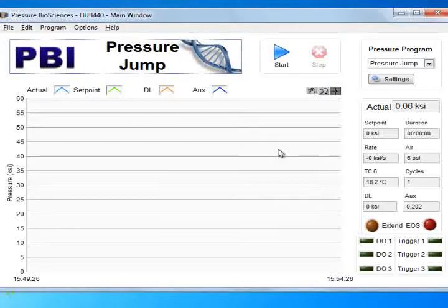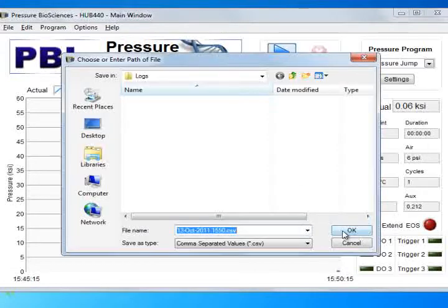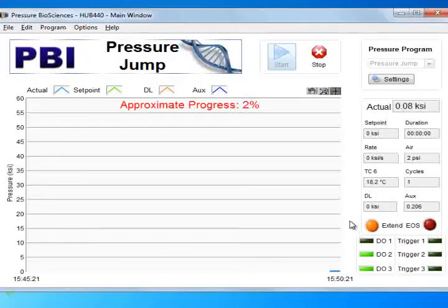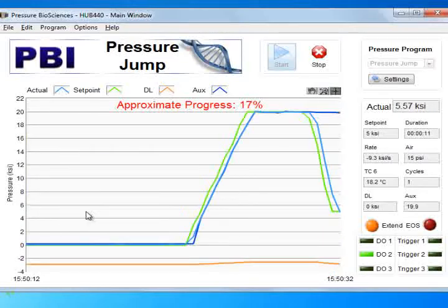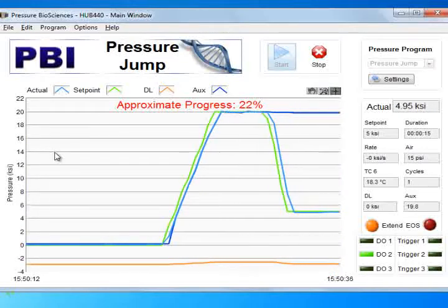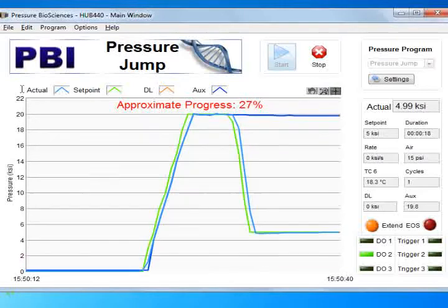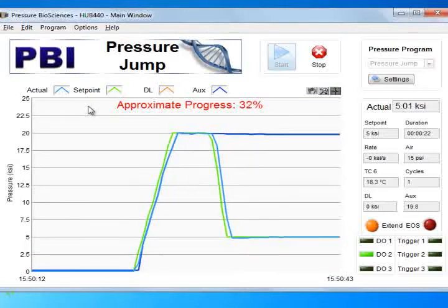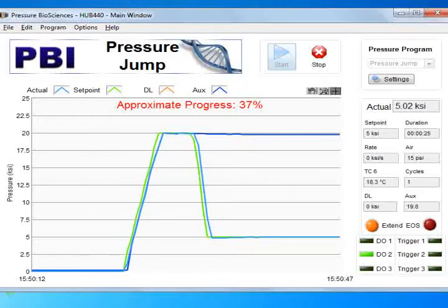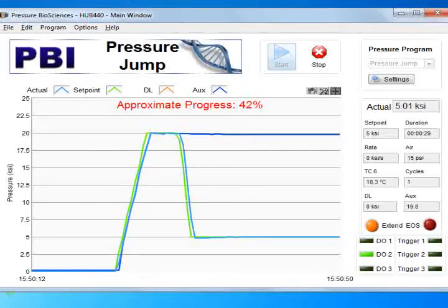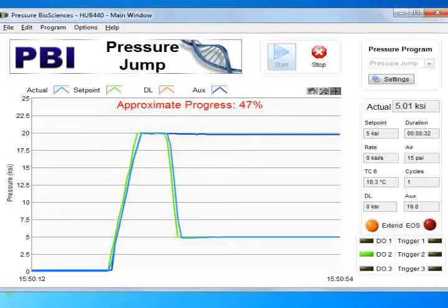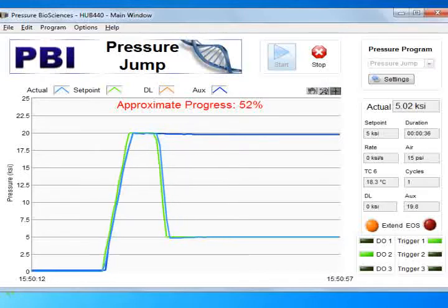Using the Visible Items menu, user can select to display the signal from auxiliary pressure transducer included in the pressure jump kit. Once again, following the prompt for the file name, the run begins. The pressure and temperature data are being logged as well. First, the system goes to 20,000 psi of pressure, then the first valve is closed, and the pressure in the auxiliary vessel is decreased back to 5,000 psi, the target pressure after the pressure jump.